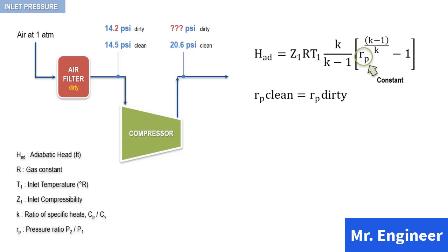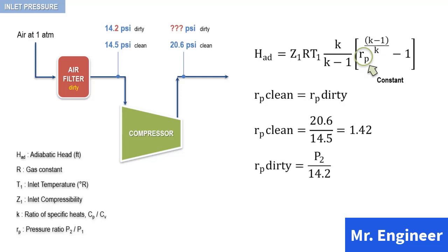The pressure ratio for the clean condition is equal to 20.6, the discharge pressure, divided by 14.5 when the air filter is clean. This gives 1.42 as a pressure ratio. The pressure ratio for the dirty condition is equal to P2, the unknown discharge pressure, divided by 14.2, which corresponds to the inlet pressure when the air filter is dirty. So P2 is equal to 1.42 times 14.2, which gives 20.2 as the new discharge pressure for the dirty filter.